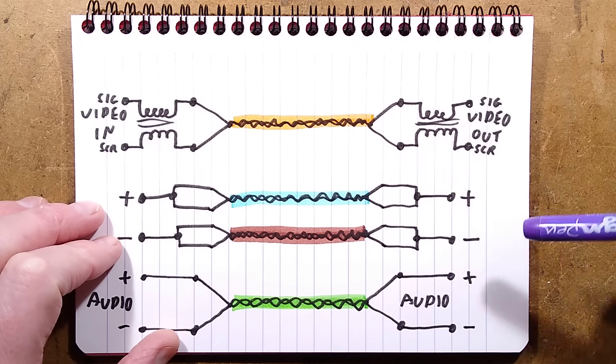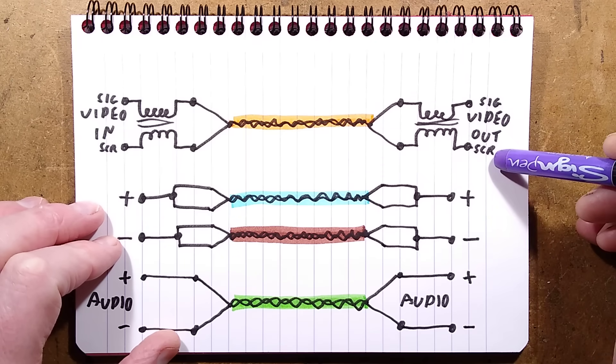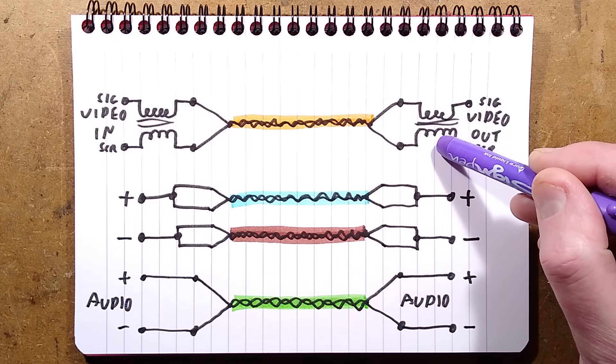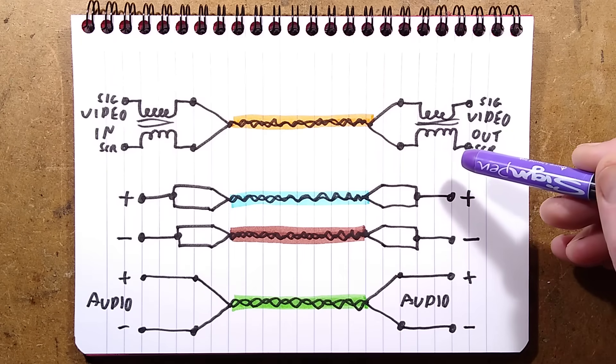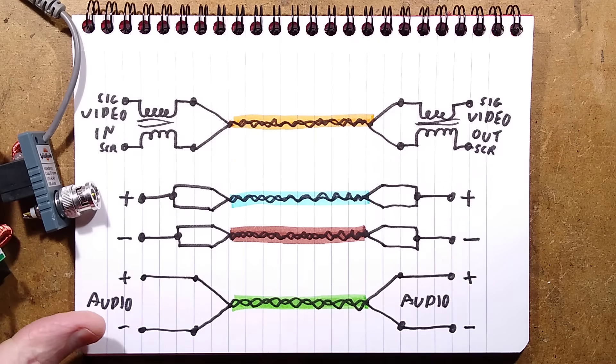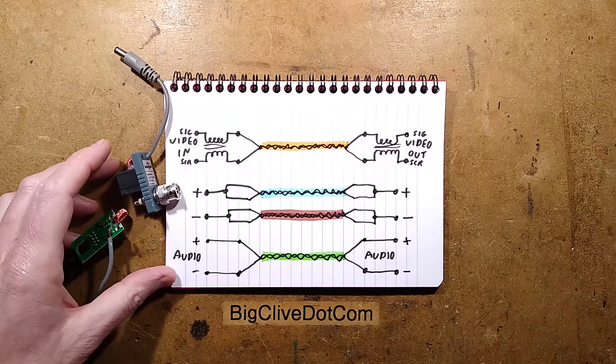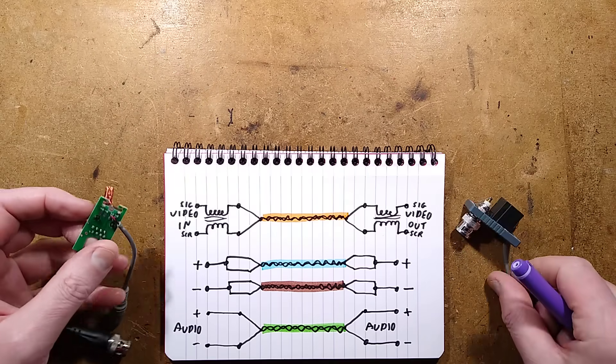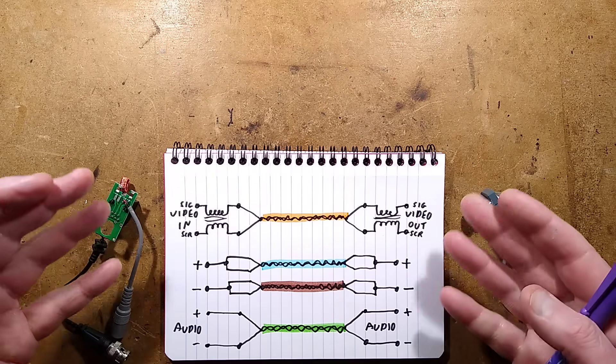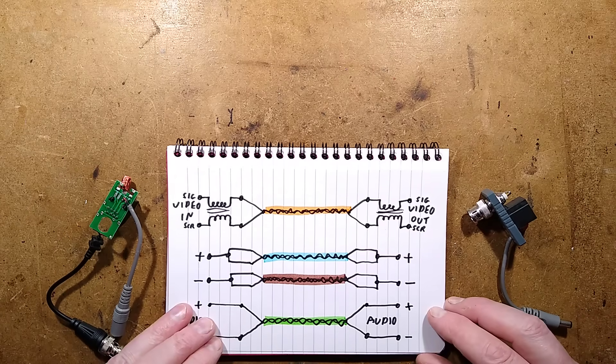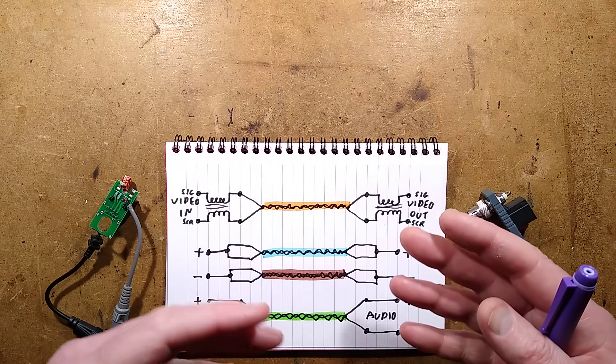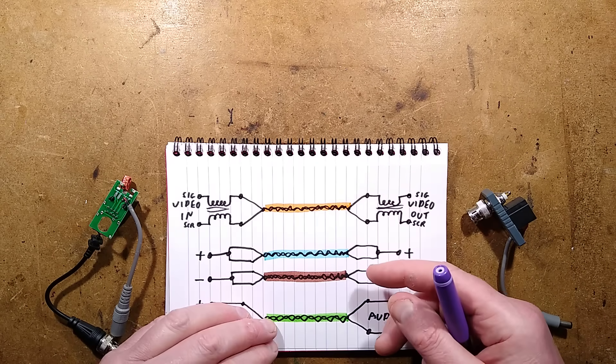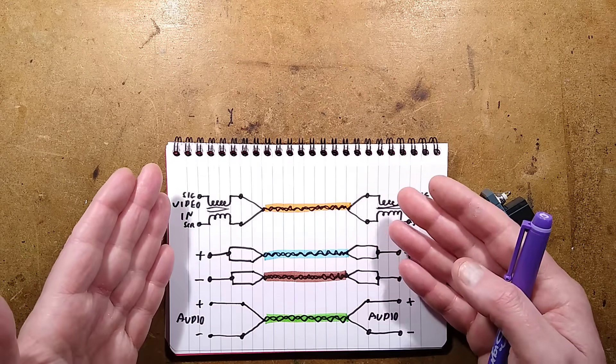It must be to do with the fact it is such a high frequency signal that would have maybe actually caused complications of a galvanic separation. But that is what's in these units. I can't really go much further - I mean it looks so simple but really the science behind it is absolutely not simple. The same with the balanced cables that we get for data networks, the RS485 and the termination resistors - that's all down to cable impedance and creating the apparent infinite length to avoid signal reflections at the frequencies we're talking about here.